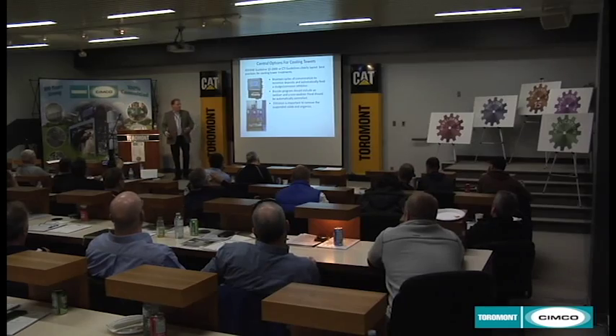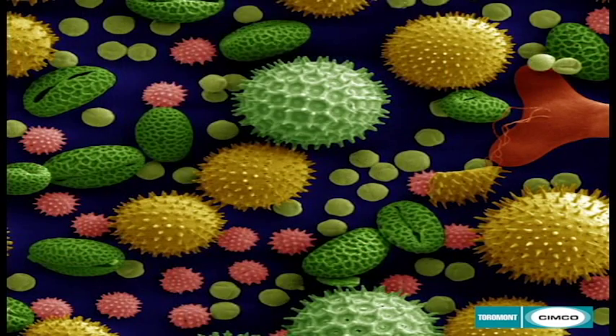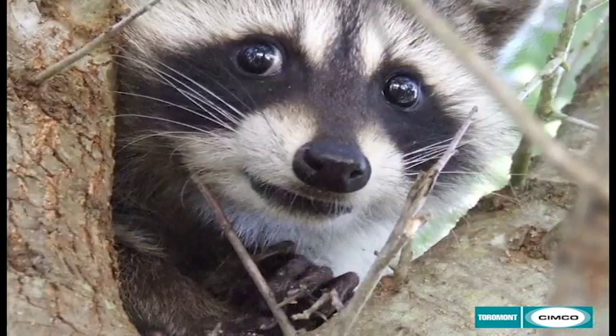Filtration is very important to remove the suspended solids. Your cooling tower or evaporative condenser is a big air scrubber. If you have a lot of construction or you're near the woods or you're near any kind of fields, you will get pollen, dust, birds, raccoons, everything in your tower. You need to filter that dirt because chemicals don't stop dirt from coming in or from settling in your tower. Remember that. Chemicals don't treat dirt. Scale, corrosion, and microbiological. I never said dirt.